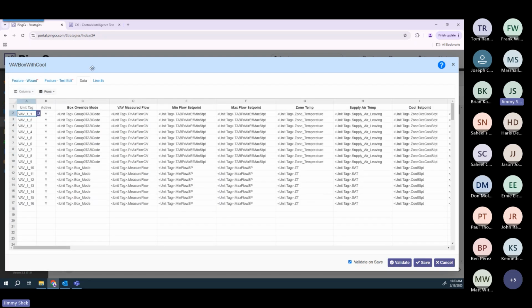We go to the data file. Here is where you map those placeholders, which are listed here on top, to the actual units and points from your system. So we see here for VAV 1-1, the box override mode point was labeled as group 0 tab code, right? And the measured flow was labeled as primary airflow CV. Whereas VAV 1-10, it's called box mode and measured flow, right? So it doesn't matter what type of controls you're using or manufacturer, or if you have a mixture of VAV boxes and controllers, whether you're dealing with retro-commissioning sites where you have some legacy controllers versus new controllers, it doesn't really matter. Once you have that test scenario written, you're simply doing the mapping between the placeholder and, in that particular unit, the points that are associated with that unit.